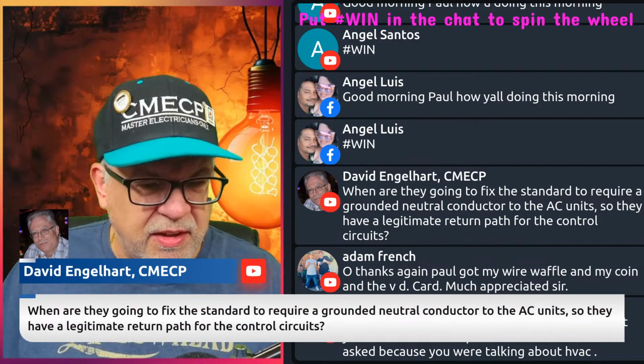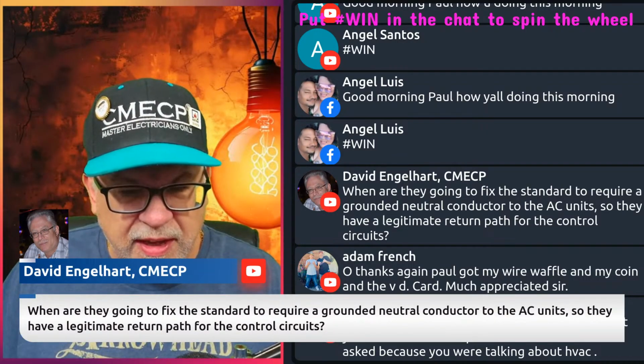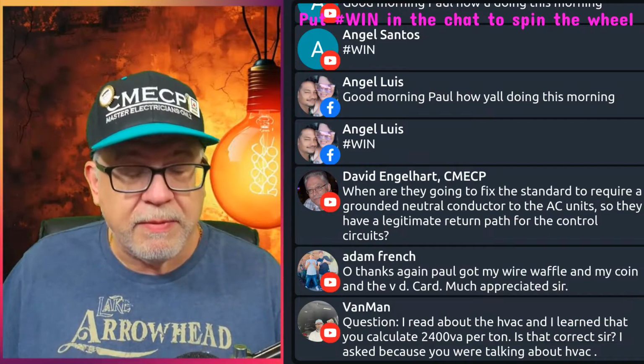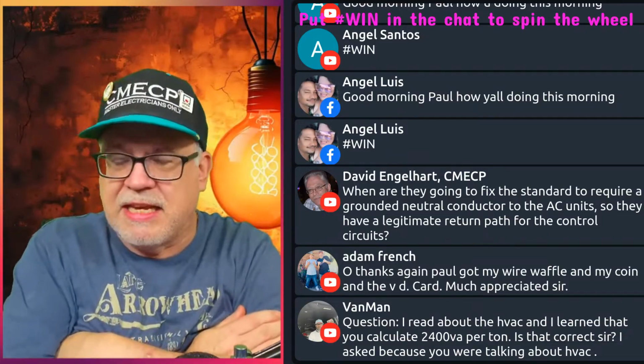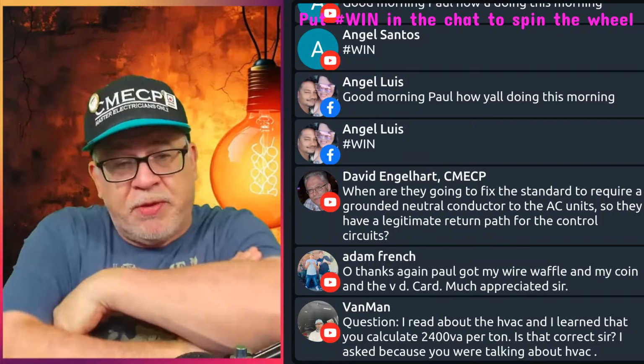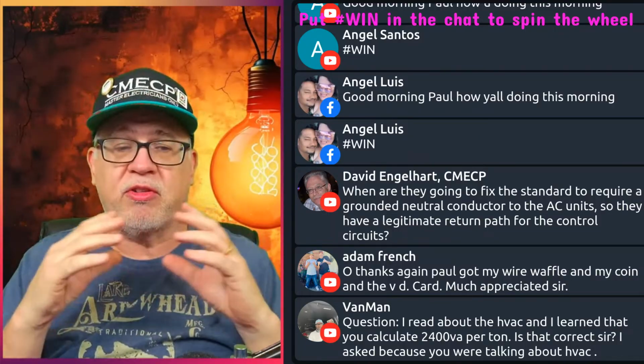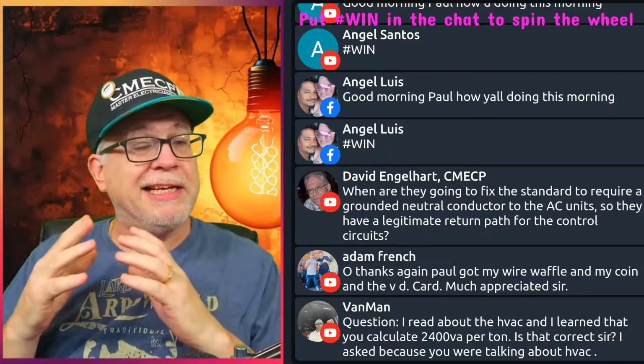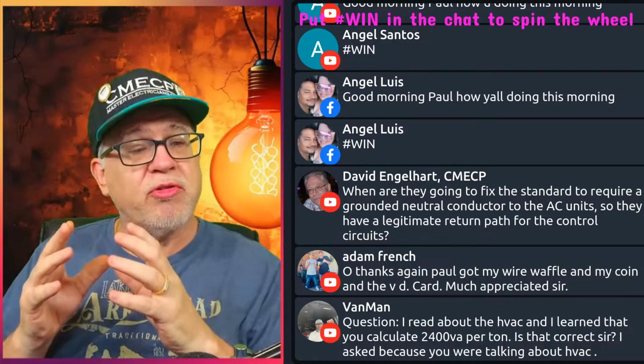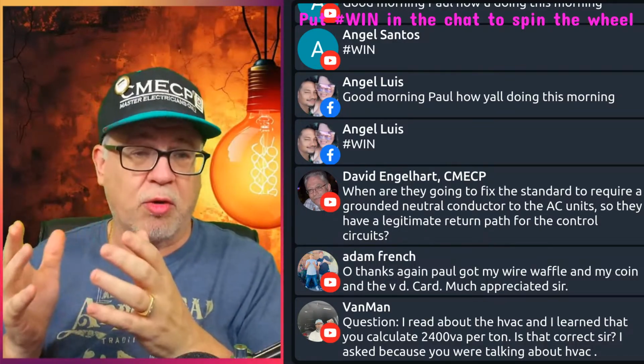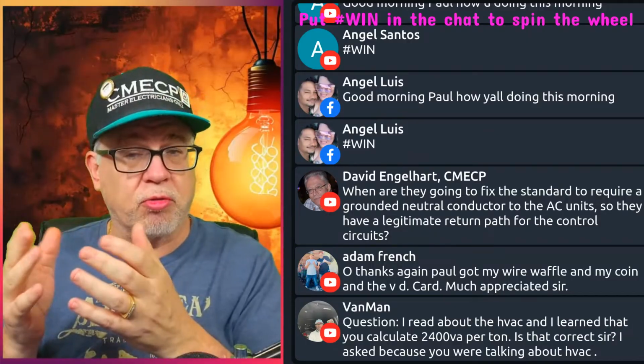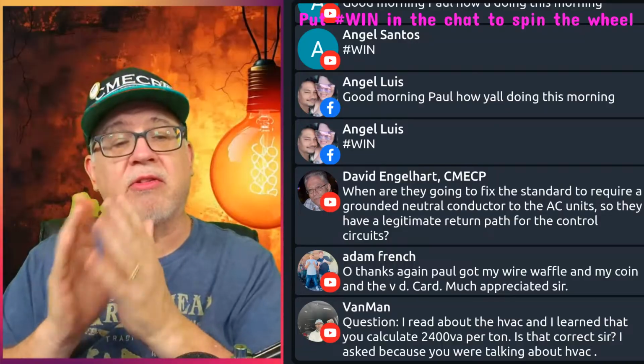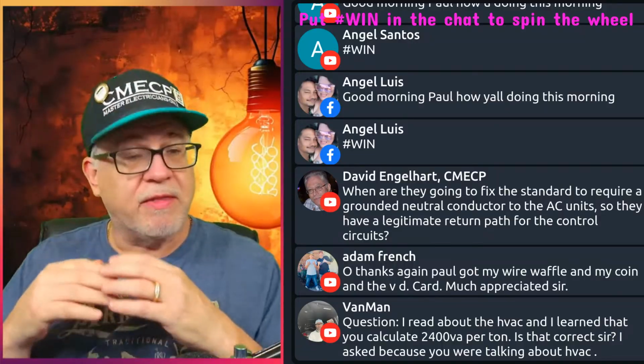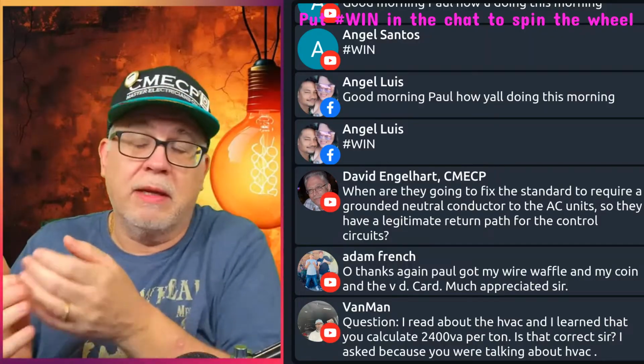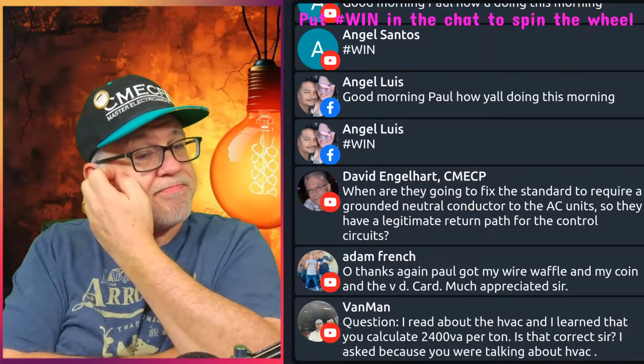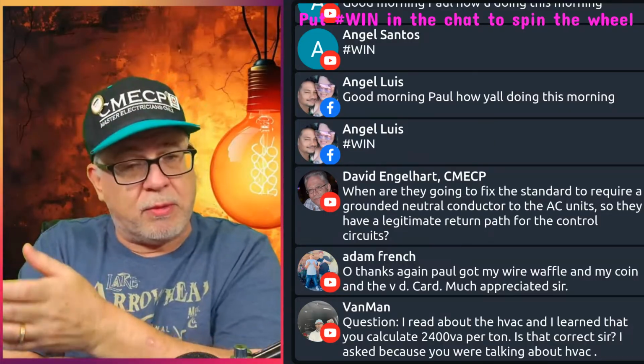Let's see here. David says, when are they going to fix the standard to require a grounded neutral conductor to the AC units so they have a legitimate return path for the control circuit? Thing to remember, really, David, is with GFCI protection, if it's pure 240, it can measure the difference, except in the panel where the GFCI is, as long as you take the pigtail over to the neutral bus. In most of them, you've got to check which device you're using, but most of those GFCIs don't need a neutral for that. You still have to have your equipment ground. You have to have that anyway, but they don't have a need for the neutral, so you wouldn't have to run a neutral in that pure 240 volt circuit. It can measure the imbalance or leakage current on the frame through the equipment ground. They will function fine without a neutral because they don't need a neutral. But there are other issues that they're running into upstream of these things that are affecting the high frequencies and all this.